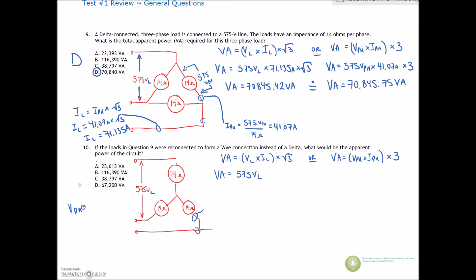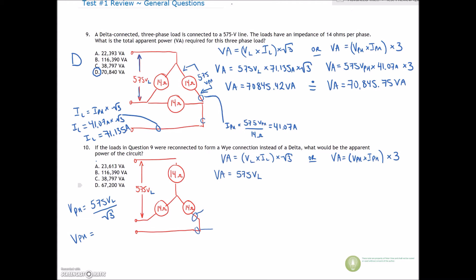So let's find the phase voltage. Our phase voltage is equal to our line voltage of 575 volts divided by √3. These are funky voltages, but let's work with them. 575 divided by √3 gives us 331.98 volts — that's the voltage across any of these phase impedances.